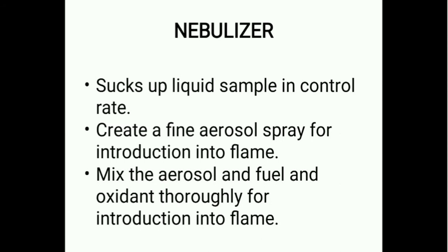Then we have a nebulizer. The nebulizer sucks up the liquid sample at a controlled rate and creates a fine aerosol spray for introduction into the flame. It mixes the aerosol with the fuel and oxygen thoroughly for introduction into the flame.